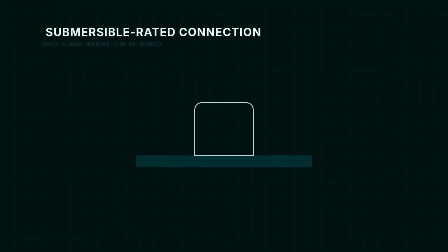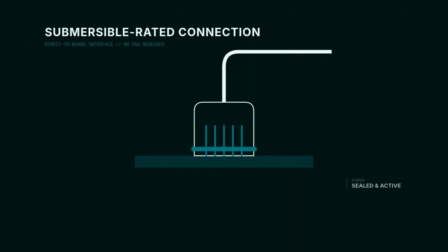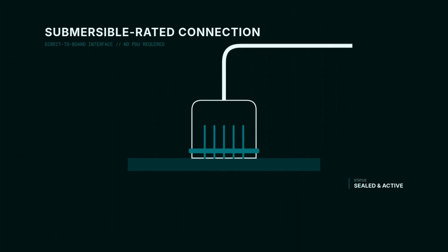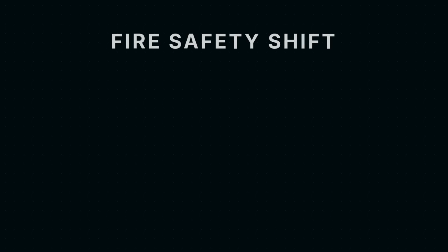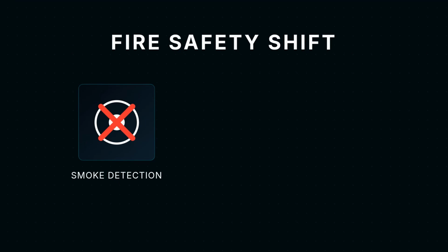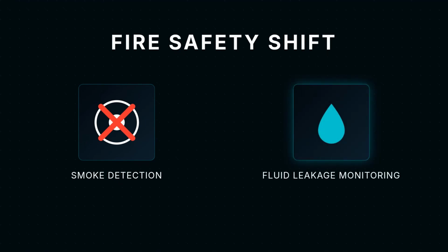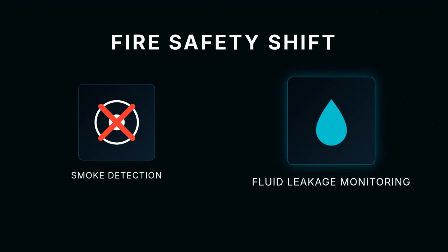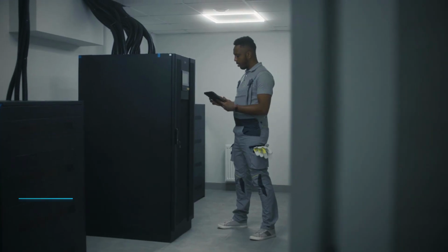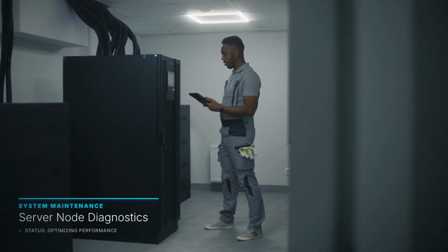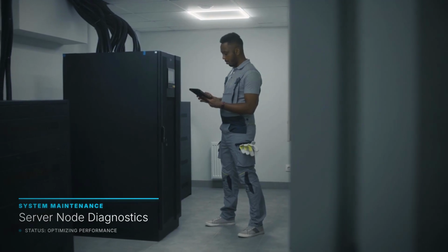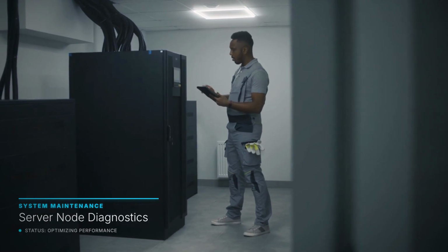Electrical distribution shifts to submersible-rated connections inside the tank, with no PDUs required at the rack level. Fire safety shifts too, from smoke detection in an enclosed space to fluid leakage monitoring in an open room. Operations change as well, requiring tank lifting mechanisms and fluid drainage protocols before maintenance.